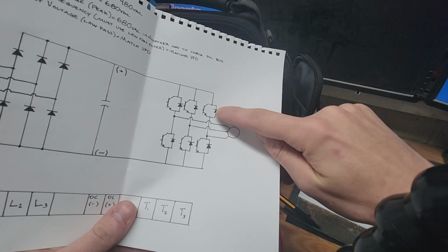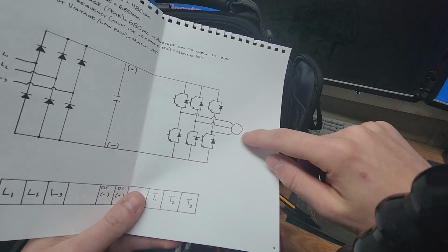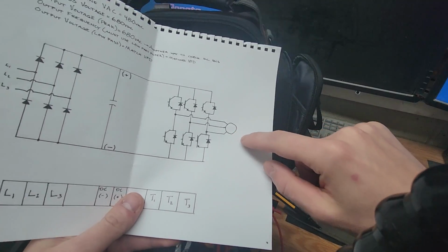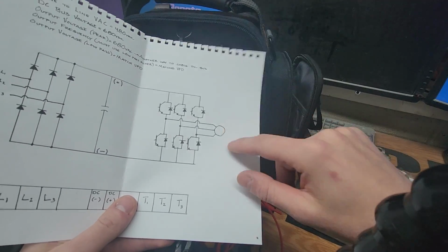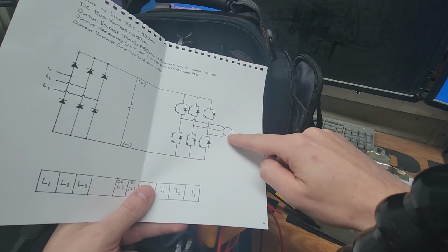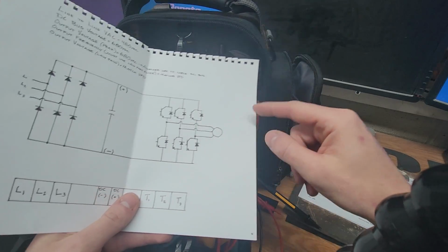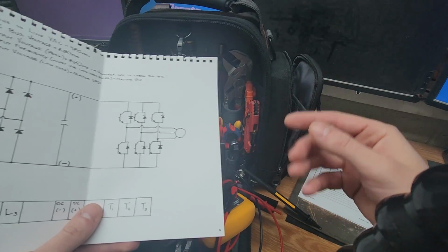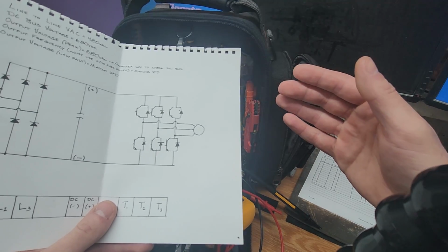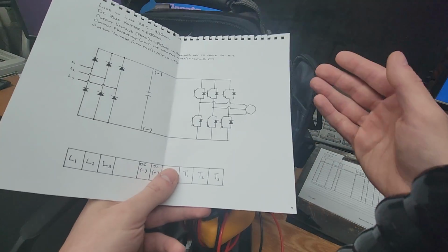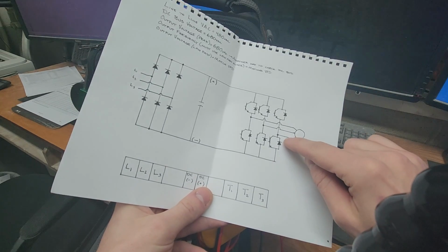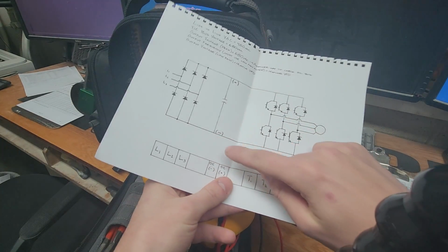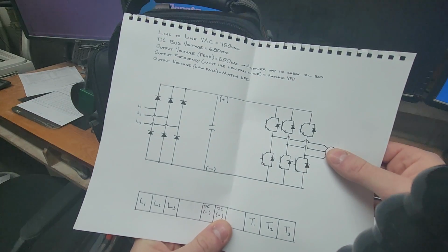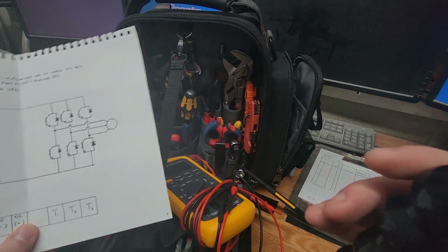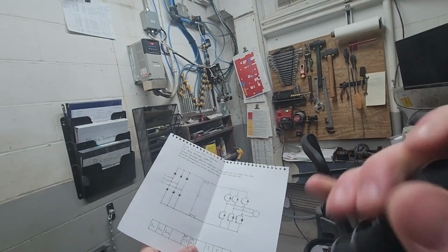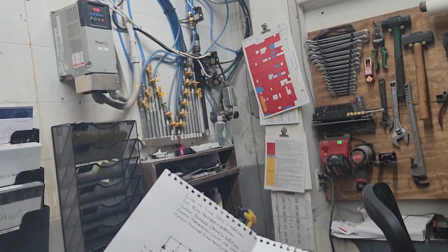Flyback diodes are used on IGBTs when your IGBTs are feeding an inductive load. So induction motor, induction load, you need a flyback diode, and the reason for that is if you don't have a flyback diode, you'll get these crazy high voltage spikes, and you'll basically fry everything. So we'll be testing these diodes, voltage, and some other stuff. So we'll pan over to the VFD we're going to look at today and go from there.